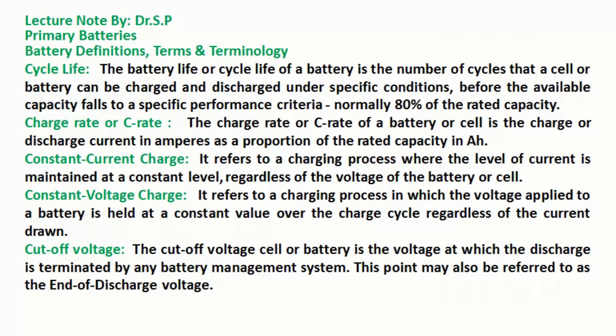Cycle life: the battery life or cycle life of a battery is the number of cycles that a cell or battery can be charged and discharged under specific conditions before the available capacity falls to a specific performance criteria, normally 80 percent of the rated capacity. Charge rate or C-rate: the charge rate or C-rate of a battery or cell is the charge or discharge current in amperes as a proportion of the rated capacity in Ah.